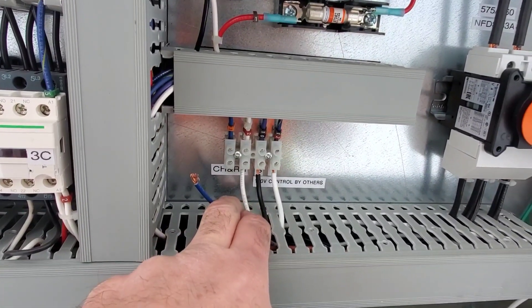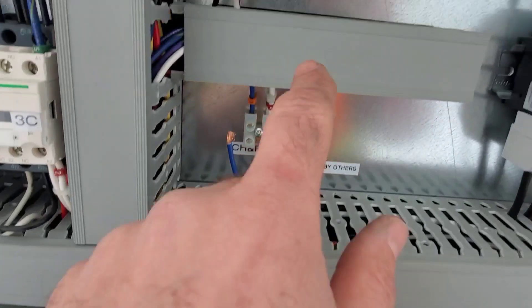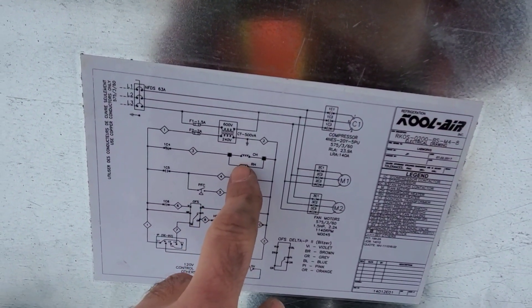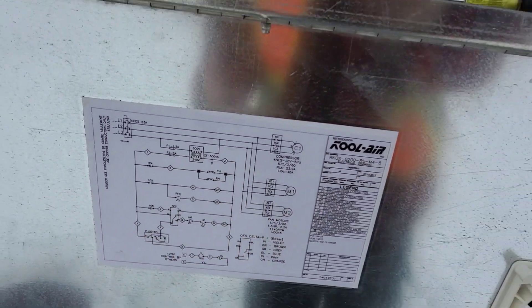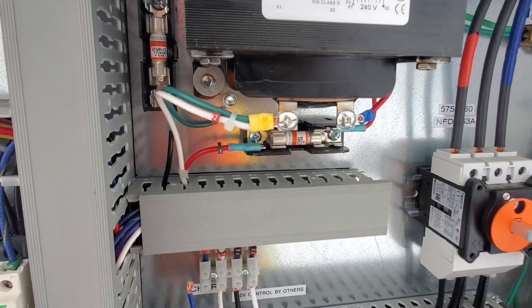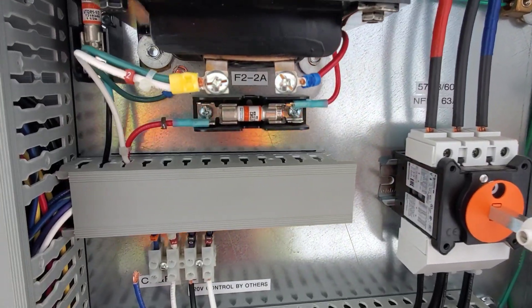This wire here is going to the crankcase heaters. If I meter that wire out, it reads bad. If we look at the diagram, it goes from number one — here — to the crankcase heater and the receiver heater. So I have to go into the compressor compartment, figure out which one is causing the issue, and get this fuse replaced, which is on its way — a coworker is bringing me a whole box of them, just in case.